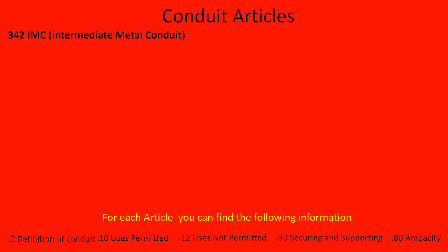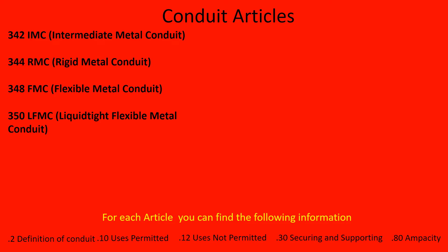The first one is Article 342, IMC, intermediate metal conduit. 344 is RMC, rigid metal conduit. 348 is FMC, flexible metal conduit. 350 is LFMC, liquid tight flexible metallic conduit — that's what we call seal tight. It's the flex with the metal inside, the liquid tight flex that has the metal inside of it.